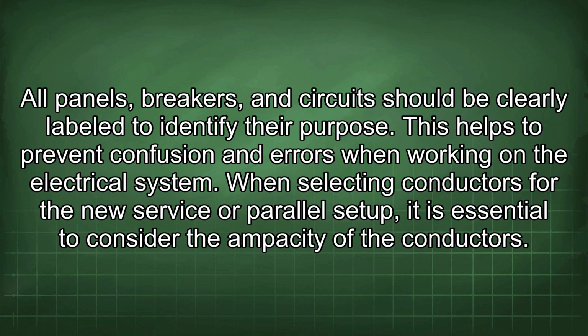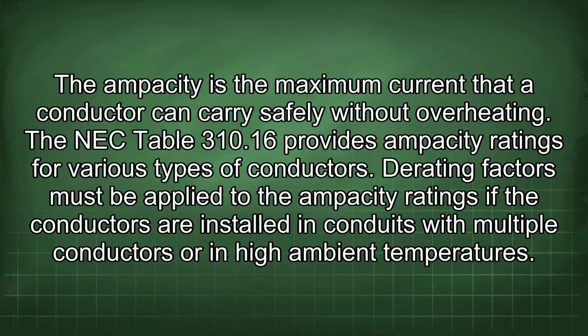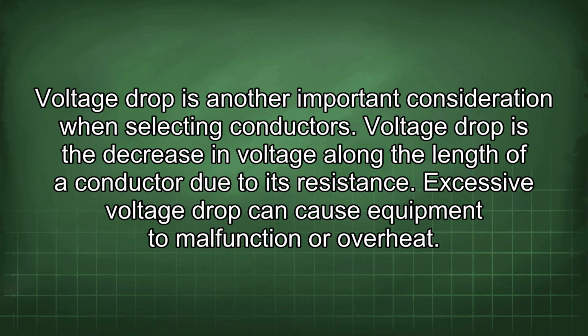When selecting conductors for the new service or parallel setup, it is essential to consider the ampacity of the conductors. The ampacity is the maximum current that a conductor can carry safely without overheating. The NEC Table 310.16 provides ampacity ratings for various types of conductors. Derating factors must be applied to the ampacity ratings if the conductors are installed in conduits with multiple conductors or in high ambient temperatures. Voltage drop is another important consideration when selecting conductors.